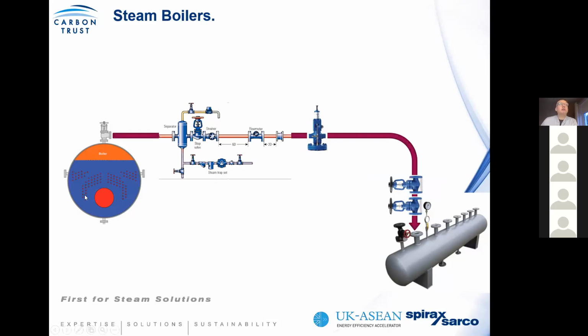Within the boiler, what we are trying to do is generate high quality steam. However, its ability to generate pure, dry, 100% dryness fraction steam is determined by its load factor or duty. In other words, how it operates in response to process demands. If the process demand is very erratic, there's a tendency that you would carry over water into the steam system. So it's important that you arrest this flow of water before it gets into your steam system and creates problems. So from the connection or crown valve of your boiler, you should put in a steam separator.